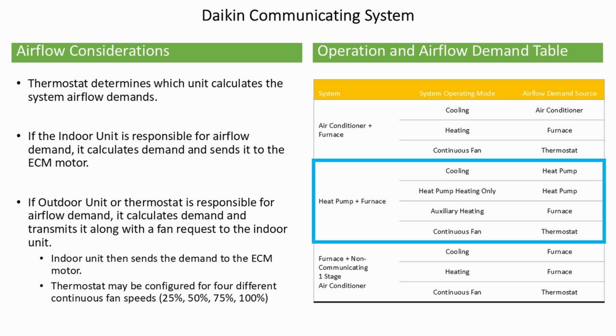For communicating heat pump and furnace, if the system operation mode is cooling, the airflow demand source is the heat pump. If the system mode of operation is heat pump heating only, the airflow demand source is also the heat pump. If the system operation mode is auxiliary heating, the airflow demand source is the furnace. If the system operating mode is continuous fan and there is no call for heating or cooling, then the airflow demand source is the thermostat.